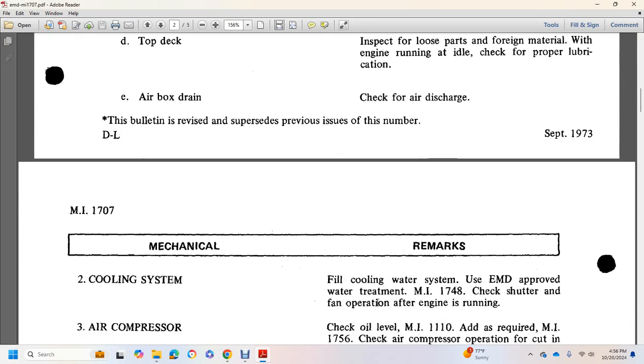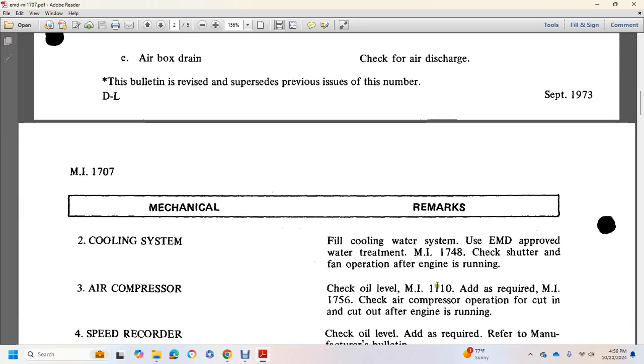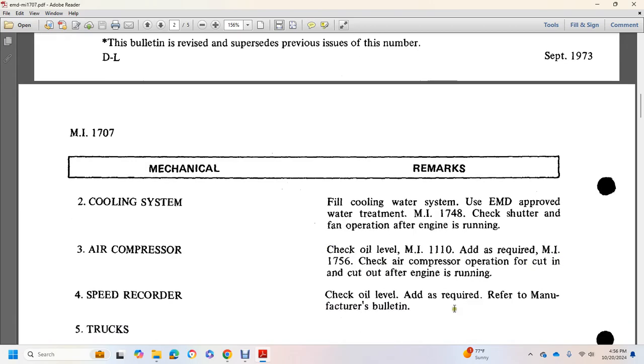Mechanical and remarks. Cooling system. Fill the cooling system with EMD approved water treatment, Maintenance Instruction 1748. Check the shutter and fan operation after the engine is running. Air compressor, check oil level, Maintenance Instruction 1110. Add as required, Maintenance Instruction 1756. Check air compressor operation for cut in and cut out after the engine is running.